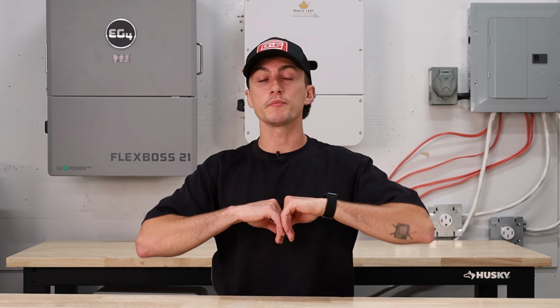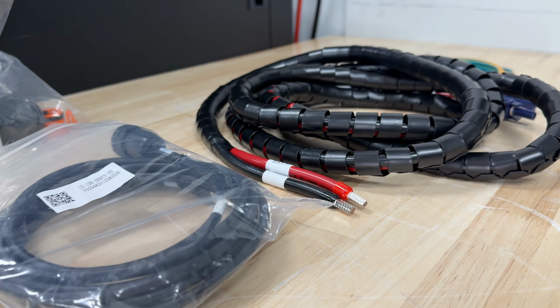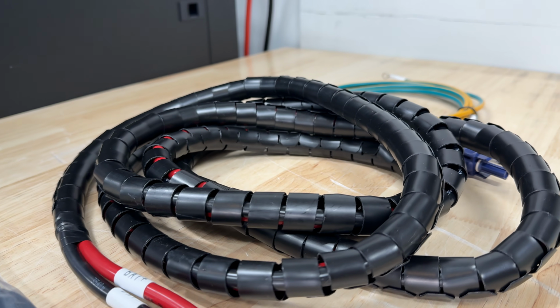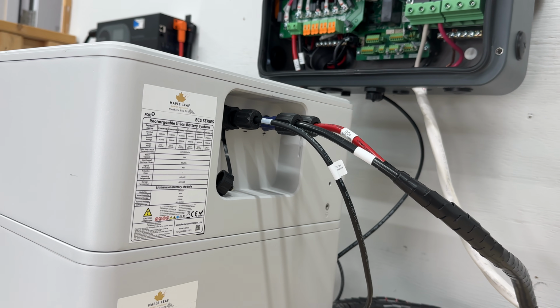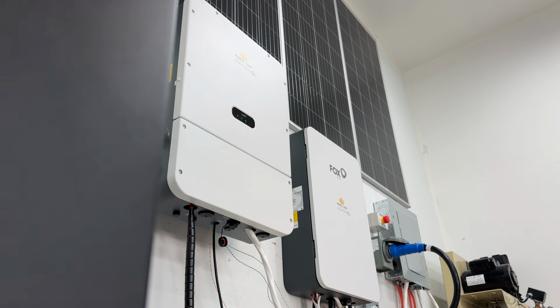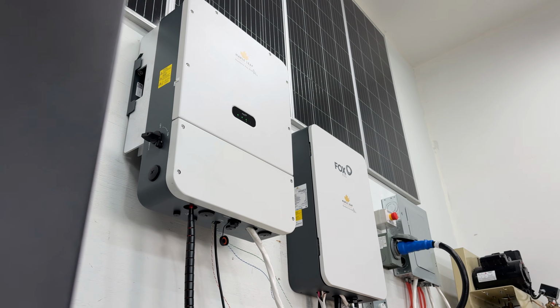One more thing we like about the high voltage system, which I touched on earlier but want to revisit, is that you can run your inverter and batteries much farther apart. Because your wires are thinner, there's less voltage drop over distance. You could literally have a battery stack in a closet and an inverter in your garage, with a good distance of wire running between them, and it's perfectly fine - it won't affect the output of your system.